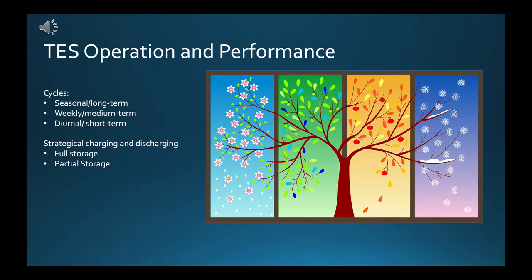For weekly mid-term storage, TES operates on weekly cycles and exhibits many of the characteristics of short-term systems. For diurnal short-term storage, TES addresses peak loads lasting a few hours to a day in order to reduce system sizing or to take advantage of energy rate structures or to allow intermittent energy sources to be used throughout the day. TES allows electricity consumption costs to be reduced by shifting electrical heating and cooling loads to periods when electricity prices are lower, usually during the night.